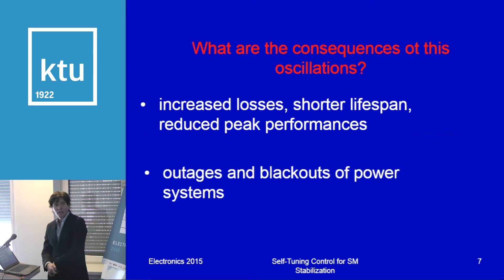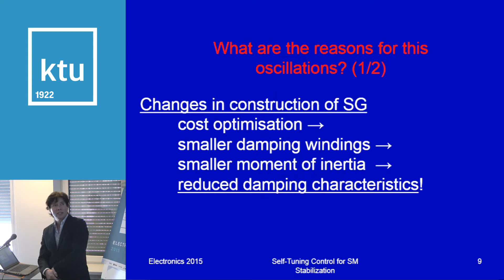So what are the reasons we have these oscillations now? We've used synchronous generators for already 120 years, but we've seen these problems only in the last 20 years. There are two main reasons. First, constructions of synchronous generators have extremely changed because of cost optimization, resulting in smaller damping windings and reduced damping characteristics.